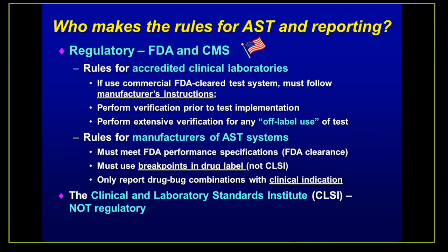We have to perform verification prior to the test implementation, and we have to perform extensive verification for any off-label use of this test. Manufacturers of AST systems must meet FDA performance specifications, so they have to receive FDA clearance. They must use breakpoints that are on the drug label, not CLSI, and they only report drug-bug combinations with the clinical indication.